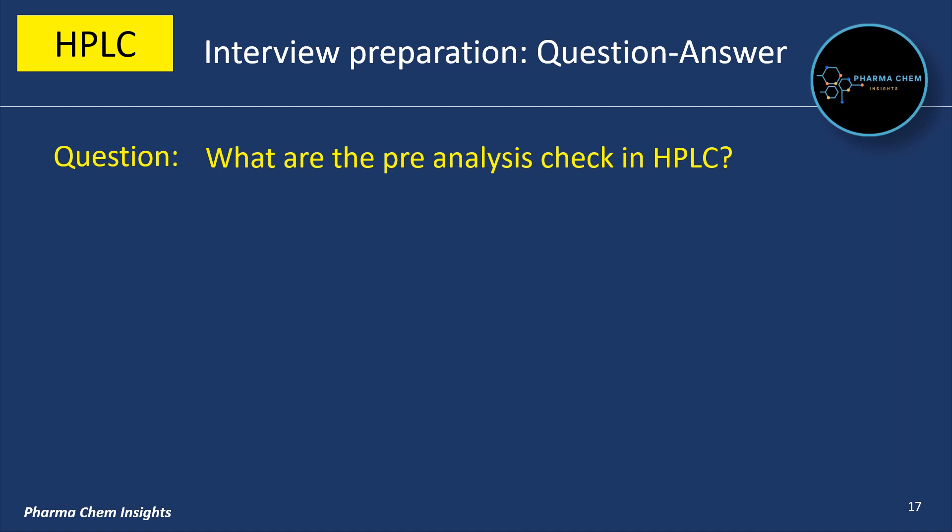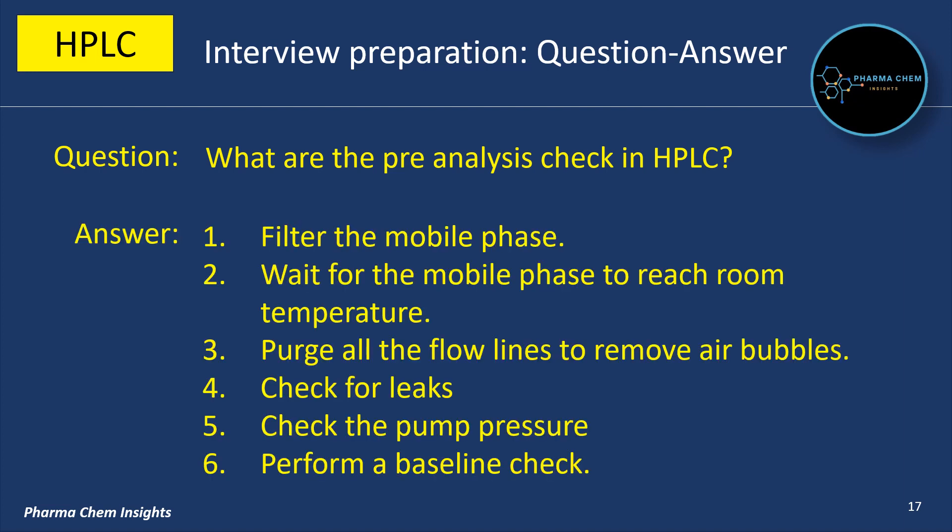What are the pre-analysis checks in HPLC? Before starting the analysis, you should: first, filter the mobile phase; second, wait for the mobile phase to reach room temperature; third, purge all the flow lines to remove air bubbles; fourth, check for leaks in the system; fifth, check the pump pressure; sixth, perform a baseline check.